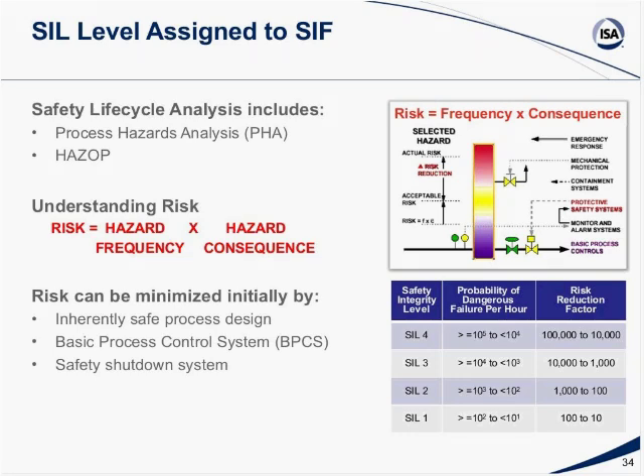So you have various SIL levels over here, as you see. It's from SIL 1, SIL 2, SIL 3, SIL 4, where SIL 4 usually indicates operations which involve maybe a nuclear process. But SIL 3 would be probably a less complicated one, where most of the oil and gas and refinery operations require SIL 3. So this is how a SIL, or safety integrity level, is determined after a proper hazard analysis is done. So it's very important to really find out what your risk is and what kind of system with what kind of SIL level is required for your particular process.